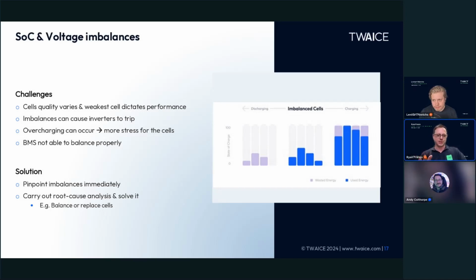One of the primary causes of unavailability is imbalance issues, either at a module level or a string level. If you look at the chart on the right, starting at the center and going right, you see elements of the battery having their state of charge reported inaccurately. When you charge, not all of the capacity is able to charge to the complete set point, 100%, for example. If you go to the left and discharge, not every element of the battery is able to discharge to its complete extent, leaving a lot of usable capacity on the table.